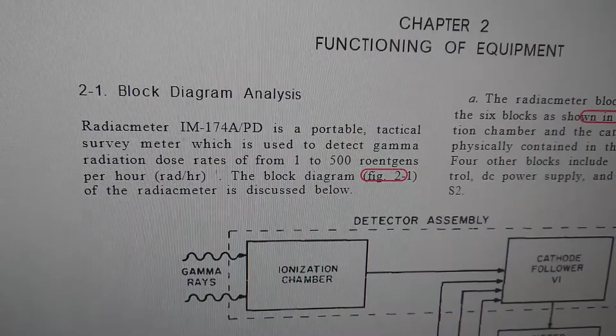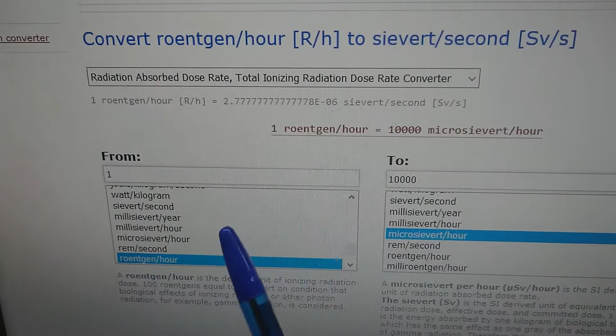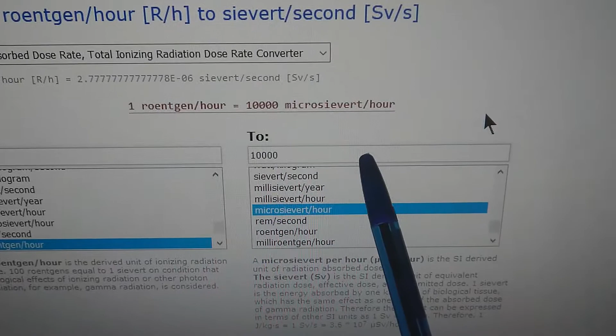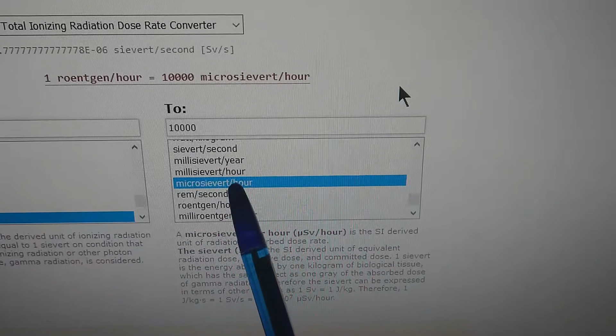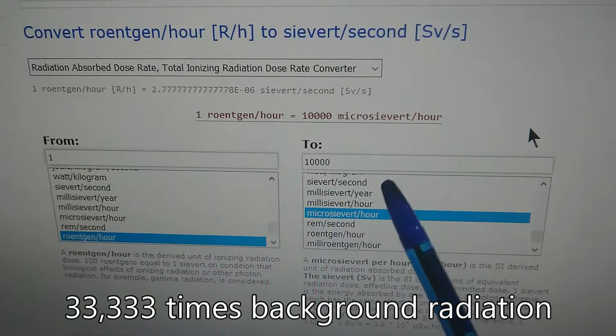Alright, so where I was referring to radiation dosage, this unit here is good for between 1 to 500 Roentgens per hour. So to give you some idea, the background radiation around here is about 0.3 microsieverts per hour. Now, 1 Roentgen per hour is about 10,000 microsieverts per hour. So for us to even hit the low end of this scale, we're in dangerous dose territory. And yeah, so probably 20,000 times or 30,000 times the radiation level that is standard background level here.